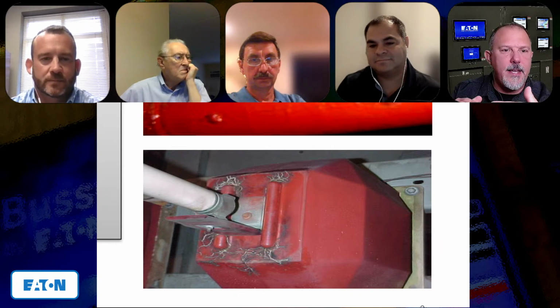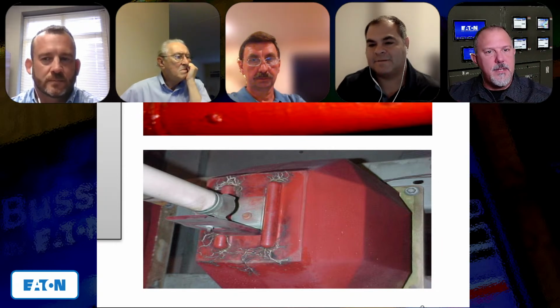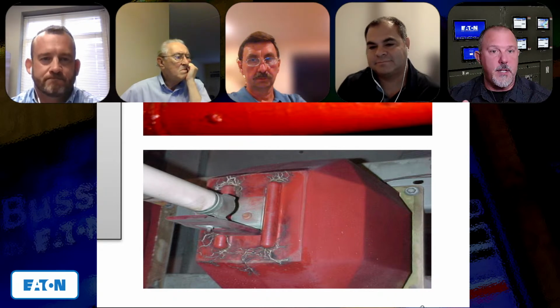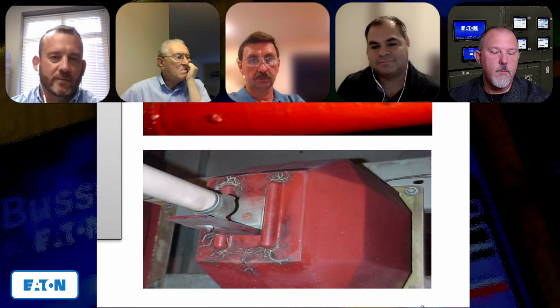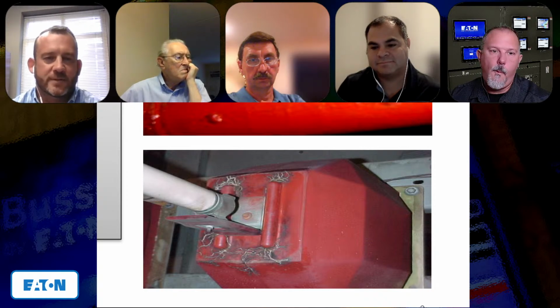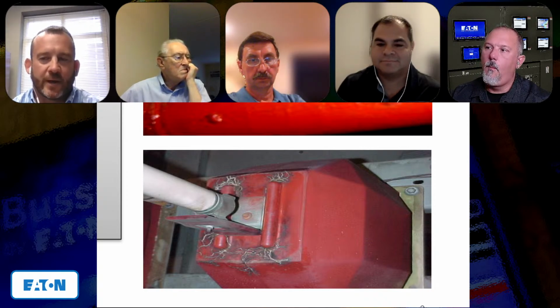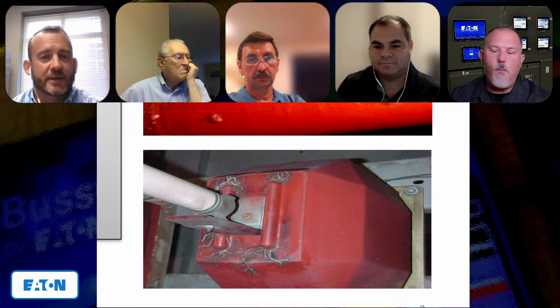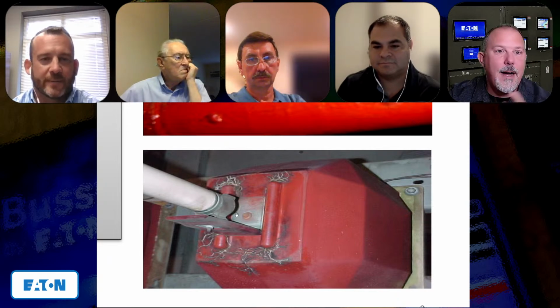Is that tracking over the top of the insulation, or is it going through the insulation? It's a little bit of both. The easiest route is across the top of the insulation, but there have been cases where it goes through the insulation too - you'll see that especially in cables.